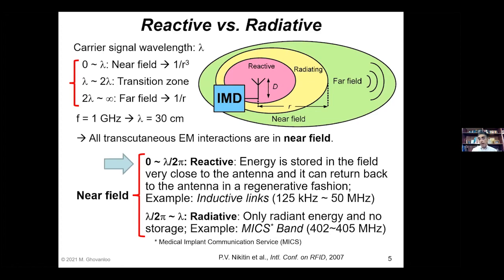The advantage of reactive wireless power transfer is that the energy is stored in a closed space around these two antennas, transmitter and receiver, and the power that is not collected by the receiver returns back to the transmitter and can be recovered. That is very important for implantable devices, because it means the efficiency could be much better, and the energy that is not dissipated in the tissue returns back to the transmitter, so you are not generating heat.